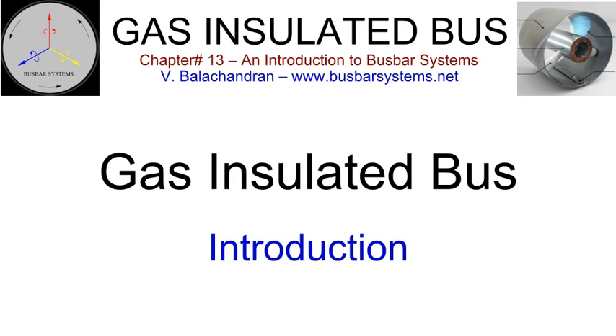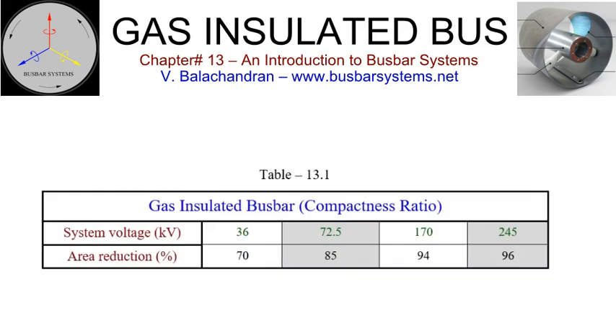Gas-insulated bus, also called gas-insulated transmission lines, was a natural extension of this idea. Gas-insulated bus have been manufactured and installed up to a rated voltage of 1200 kV and rated current of 8000 amperes. In 1975, the very first gas-insulated bus rated for 400 kV was installed in a pumped storage plant in Schluchsee, Germany. Table 13.1 details the compactness ratio for different system voltages. The compactness becomes more evident with the increase in the system voltage.